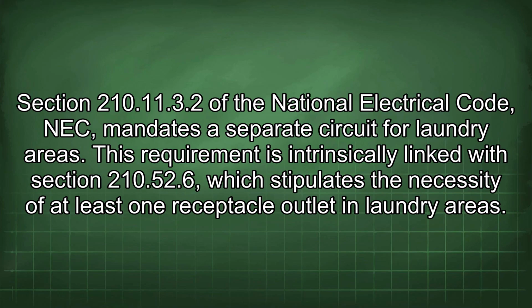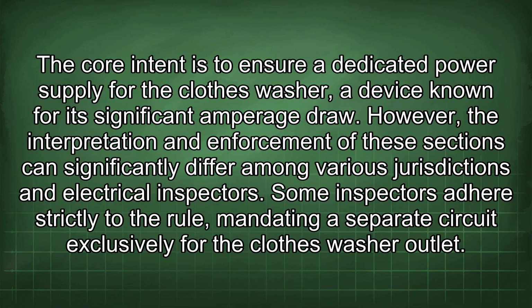Section 210.11(C)(2) of the National Electrical Code, NEC, mandates a separate circuit for laundry areas. This requirement is intrinsically linked with Section 210.52(F), which stipulates the necessity of at least one receptacle outlet in laundry areas. The core intent is to ensure a dedicated power supply for the clothes washer, a device known for its significant amperage draw. However, the interpretation and enforcement of these sections can significantly differ among various jurisdictions and electrical inspectors.